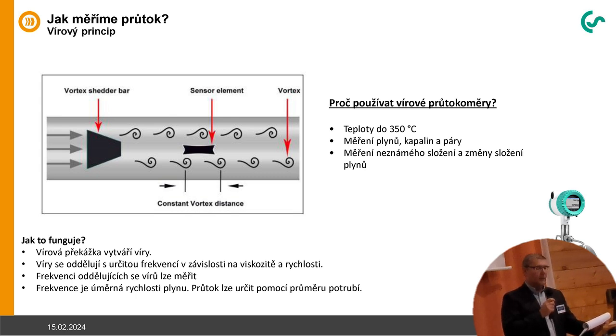How does it work? We have an obstacle, the so-called vortex shedder bar, and after the shedder bar we have the vortexes, and the sensor element is detecting the frequency of the vortexes, and this frequency can be measured. The frequency of the vortexes is more or less, let's say, proportional to the airspeed in the pipe, and if we know the pipe diameter, we can also calculate the volume flow.